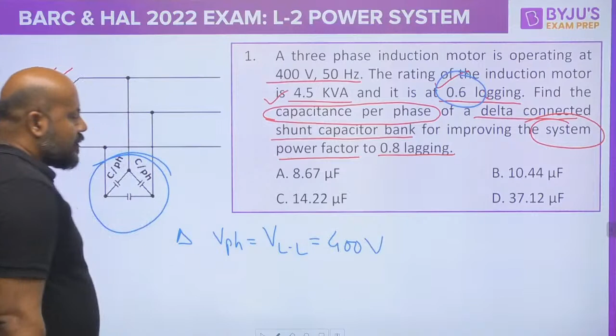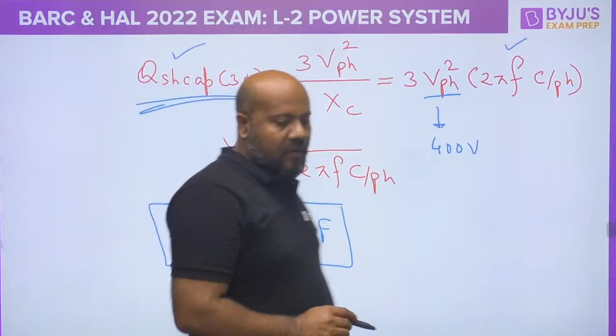So you know what is the per phase voltage, you know what is the reactive power supplied by the shunt capacitor bank, you know the frequency. So very easily you can calculate the capacitance per phase. As per my memory, it must be coming as 10.44 microfarad. Is it clear for everybody?